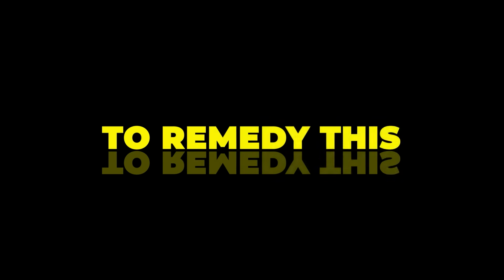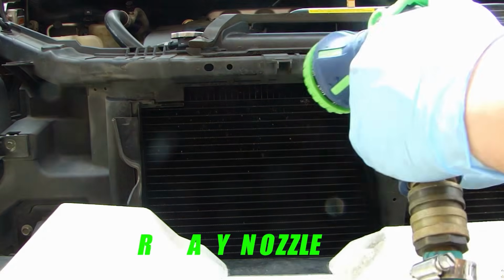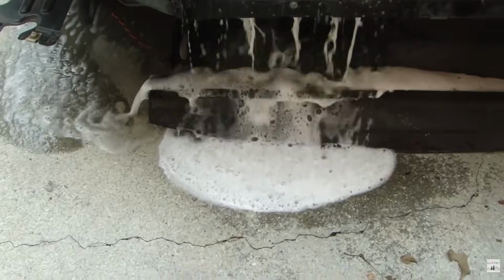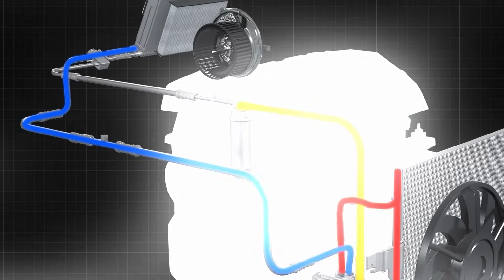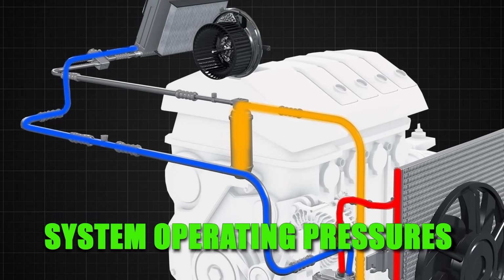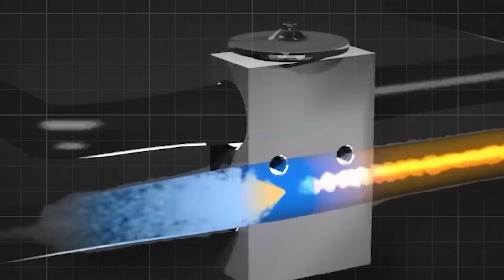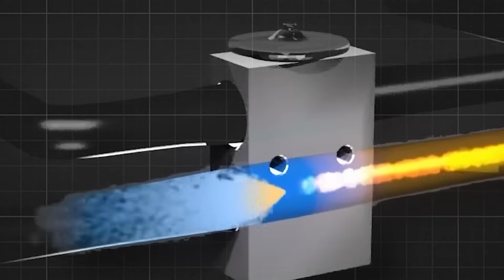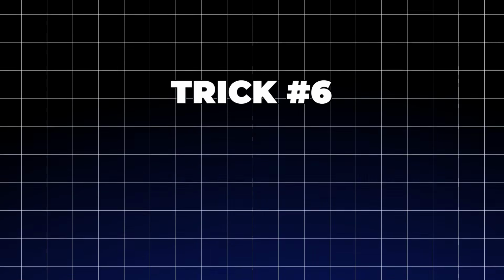To remedy this, take a garden hose with a gentle spray nozzle and flush the debris out from the back of the condenser forward. Clearing these restrictions can drop system operating pressures significantly. That allows the refrigerant to change state from a hot gas to a cool liquid much more efficiently. Trick number 6, don't blast max immediately.